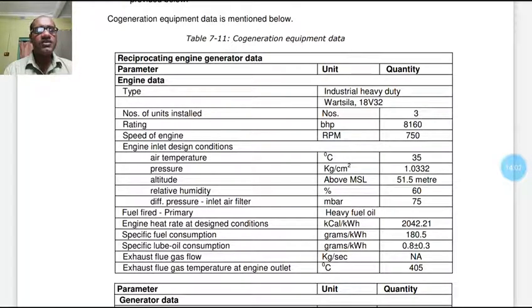Fuel fired, that is heavy fuel oil. Engine heat rate at designed condition, measured in kilocalorie per kilowatt hour, is 2042.21. Specific fuel consumption is 180.5 gram per kilowatt hour. Specific lube oil consumption, grams per kilowatt hour, is 0.8 plus or minus 0.3. Exhaust flue gas flow is not available, and exhaust flue gas temperature at engine outlet is 405 degree centigrade.